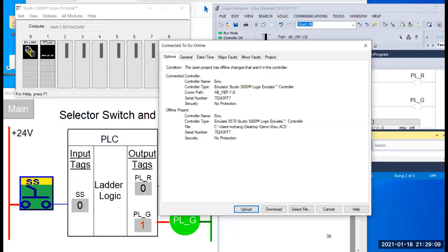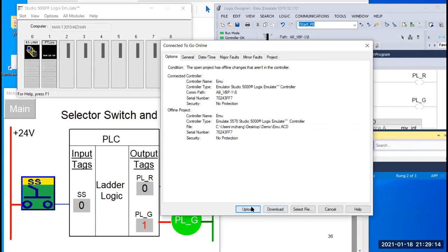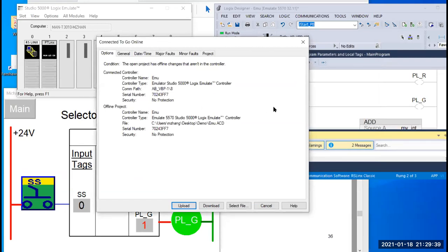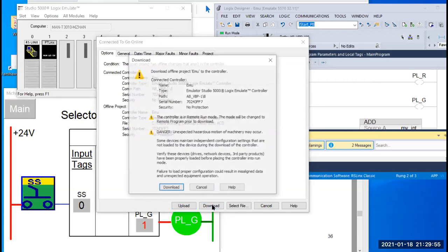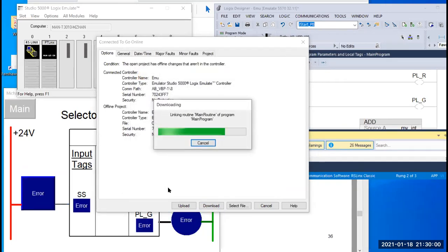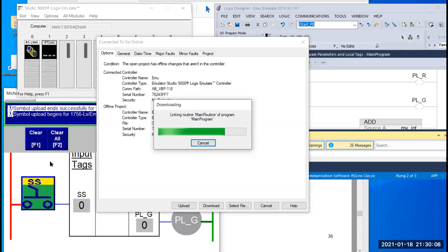The software gives you a choice: upload, download, and others — we don't need to worry about those. If you choose upload, the program will transfer from the PLC into your file, and you're going to lose what you added here — the addition instruction will be gone. If you want to keep the change, you have to choose download. Remember the direction: you transfer from your offline file to the PLC — that is download. So click download, just like a regular download, and that will change everything on the PLC memory — you can see the HMI also reflects that.